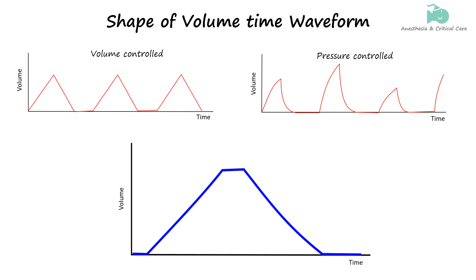Now let's study why the volume-time waveform takes the shape of a mountain. During the inspiration phase, the ventilator delivers air into the lungs, which causes the volume to increase. In volume-controlled ventilation, this increase typically appears as a linear rise on the waveform, since the ventilator is programmed to deliver a specific volume of air over a set period. The slope of this rise can vary depending on the flow rate settings — a higher flow rate results in a steeper rise.